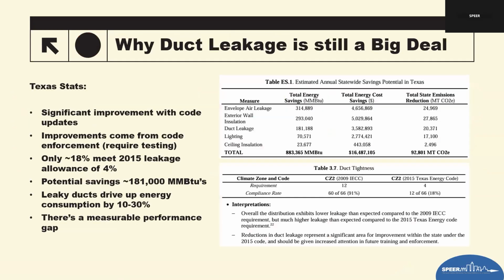Significant changes are happening with just the duct system and duct testing, so we'll roll right into that. But why is it important? Why is it still a big deal? We've seen significant improvement over time as codes have been updated, but the real gains only happen with enforcement, when it requires actual testing. When we test, performance improves, and when we don't, leakage stays high.